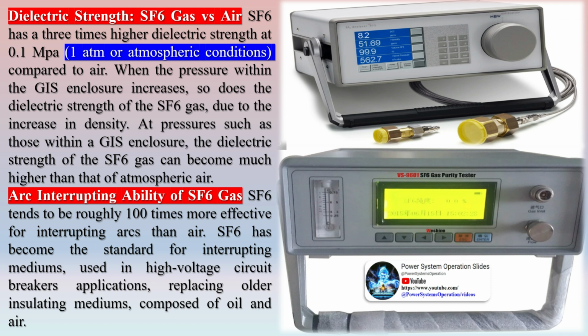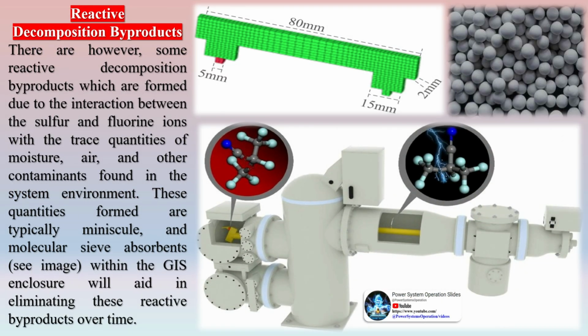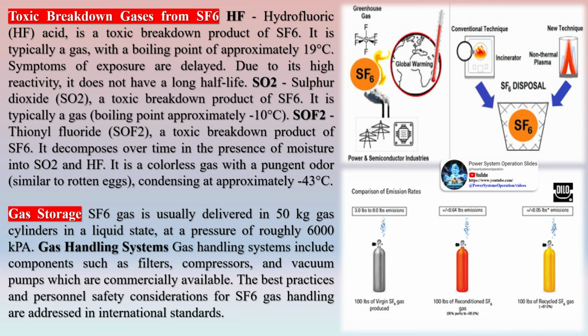SF6 has become the standard for interrupting mediums, used in high-voltage circuit breaker applications, replacing older insulating mediums composed of oil and air. There are, however, some reactive decomposition byproducts which are formed due to the interaction between the sulfur and fluorine ions with the trace quantities of moisture, air, and other contaminants found in the system environment. These quantities formed are typically minuscule, and molecular sieve absorbents within the GIS enclosure will aid in eliminating these reactive byproducts over time. Hydrofluoric acid, HF, is a toxic breakdown product of SF6.